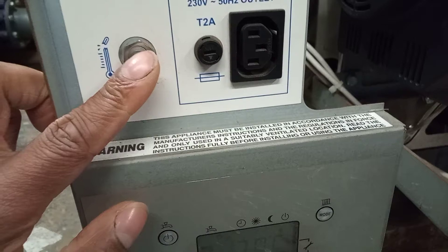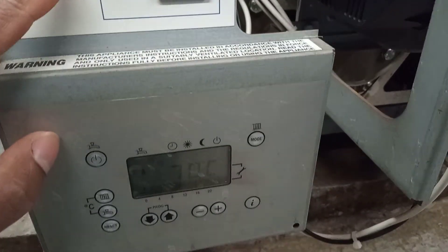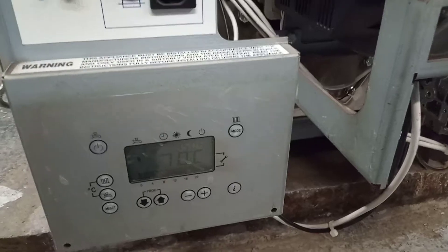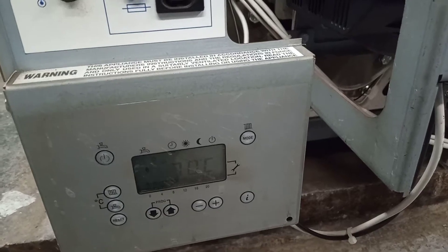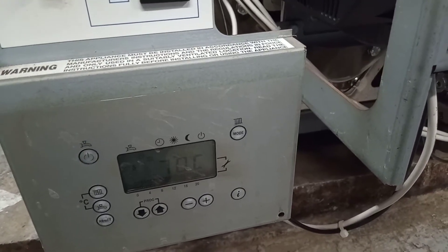This overheat was the one that needed resetting — the mechanical reset. Hit that and then the appliance was happy to start running. It hasn't locked out since. Going to see if it works without locking out, but I'm happy that it's operating well. Let's have a look inside one of these units.